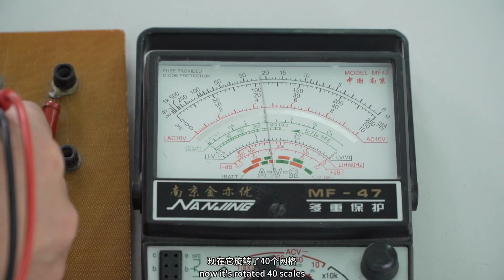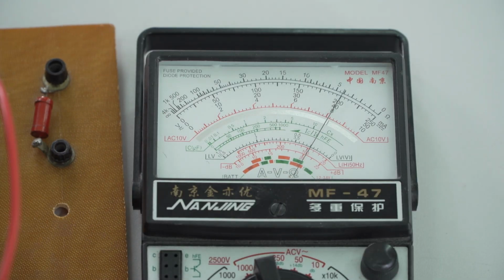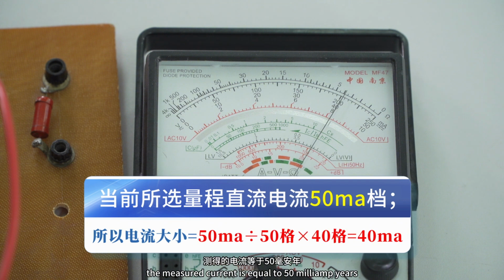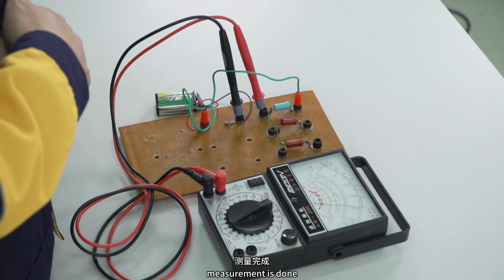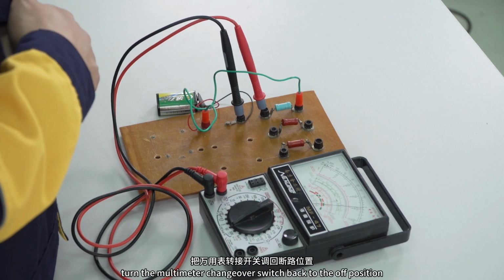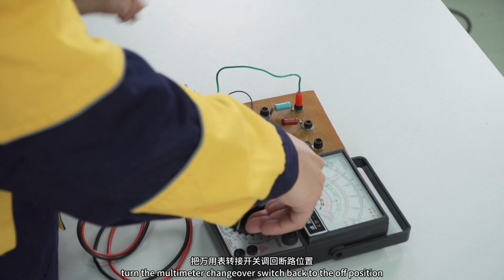Now it's rotated 40 scales. The measured current is equal to 50 milliamperes divided by 50 multiplied by 40, which is 40 milliamperes. Measurement is done. Turn the multimeter changeover switch back to the off position.